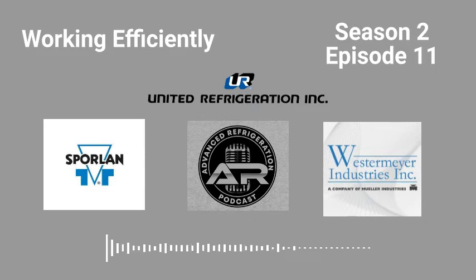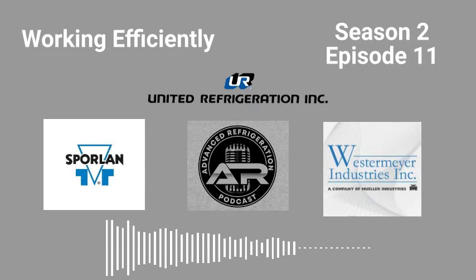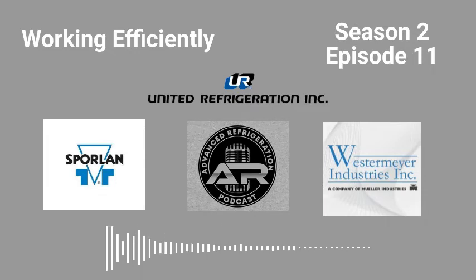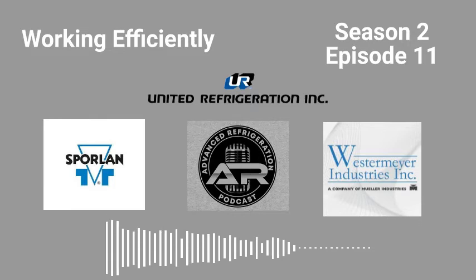One thing I found: with CO2 racks, guys waste time pulling vacuums when the manufacturer gives them a bunch of 1/4 inch ports with no 3/8 ports. So I pull the reliefs out and thread in a 1/2 inch MPT to 1/2 inch flare fitting, and now I'm pulling vacuums off that. I've saved so much time on jobs just doing that — we get vacuums done in half the time other guys take, because we're pulling off 1/2 inch ports instead of 1/4 inch ports. Stuff like that saves time.